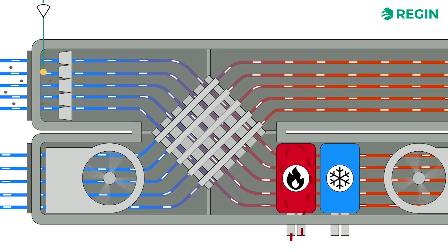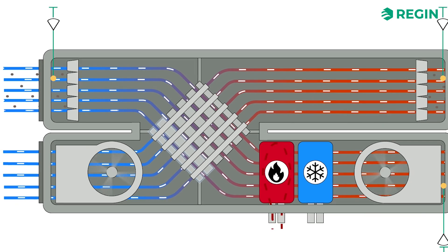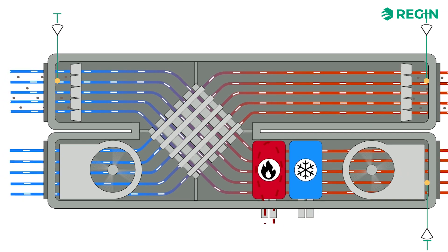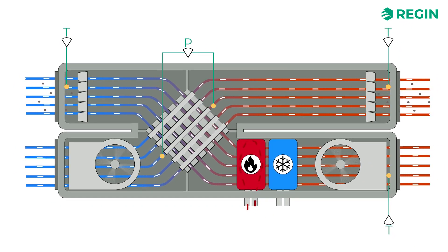This process is a delicate, continuous interplay of measuring pressure and opening and closing bypass dampers. Since the airflow through the exchanger is affected by frost, the air pressure is measured at points before and after the exchanger. A small pressure difference of only 5 to 10 Pascal indicates frost, if it can be detected. The higher accuracy of measurement, the sooner frost can be detected and counteracted. Since it takes a lot less energy to thaw just frost compared to fully frozen ice, precise measurement equals less energy waste.